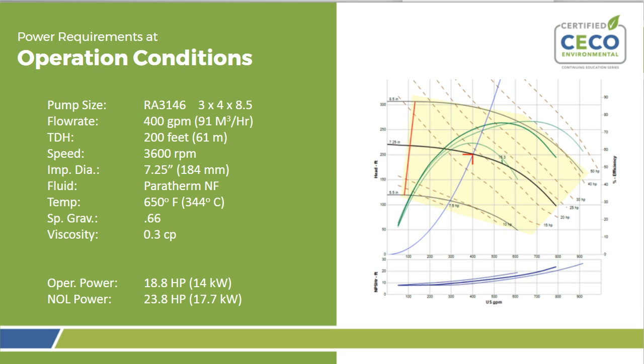Let me switch slides here. So for typical operating conditions, we have a typical pump, a 3x4x8.5 pump. We want 400 GPM at 200 feet of head. We're spinning at 3,600. We have our impeller diameter. The fluid is a thermal fluid, let's say a Paratherm NF in this case, and the temperature that it's running at is 650 degrees. The specific gravity of that Paratherm is 0.66 at that temperature. The viscosity is 0.3, a very, very thin fluid, and very, very light. Those are your operating conditions.